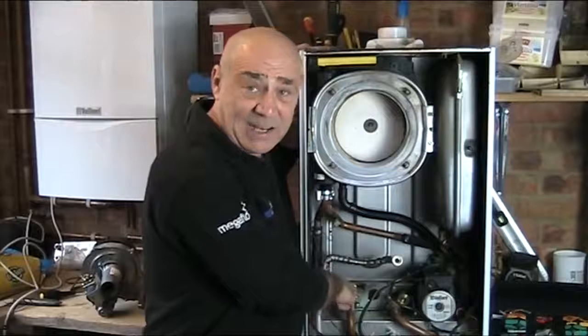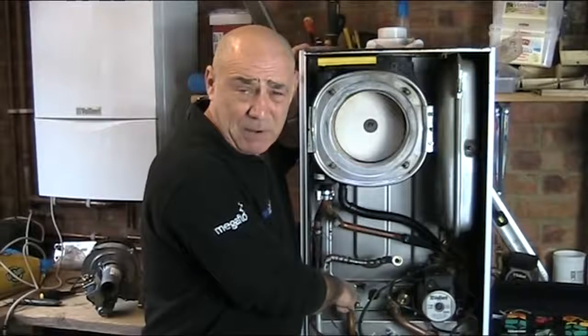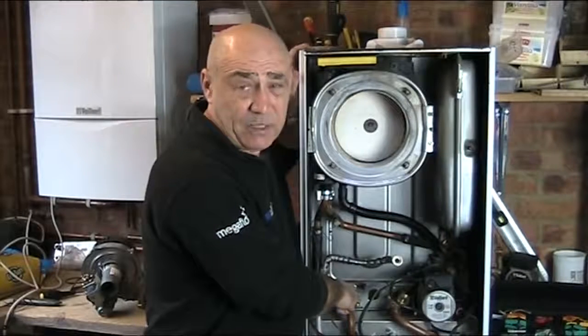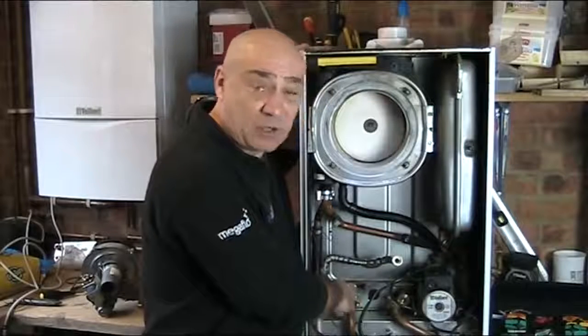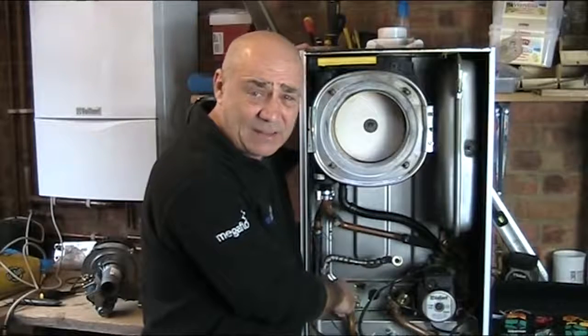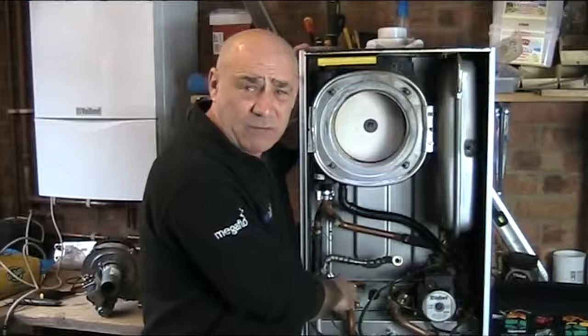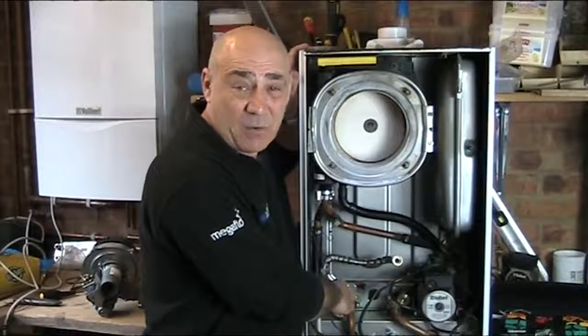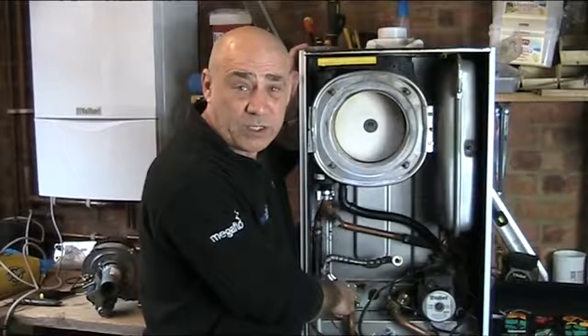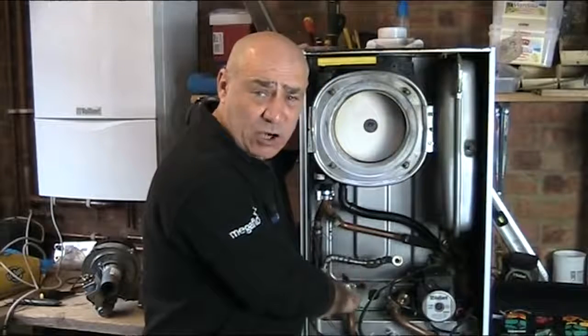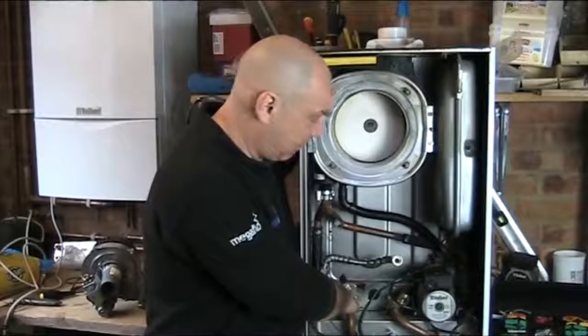Then, while we've got it drained, we remove the digital sensor and we check the filter, clear it, clean it, and if required, if the sensor is badly blocked, which it will be, even on a clean system, sometimes we need to replace that so that we know we're not going to get any horrible or nasty recalls later on, especially in the winter when it's very cold. So that will get serviced and checked in the hydro block.